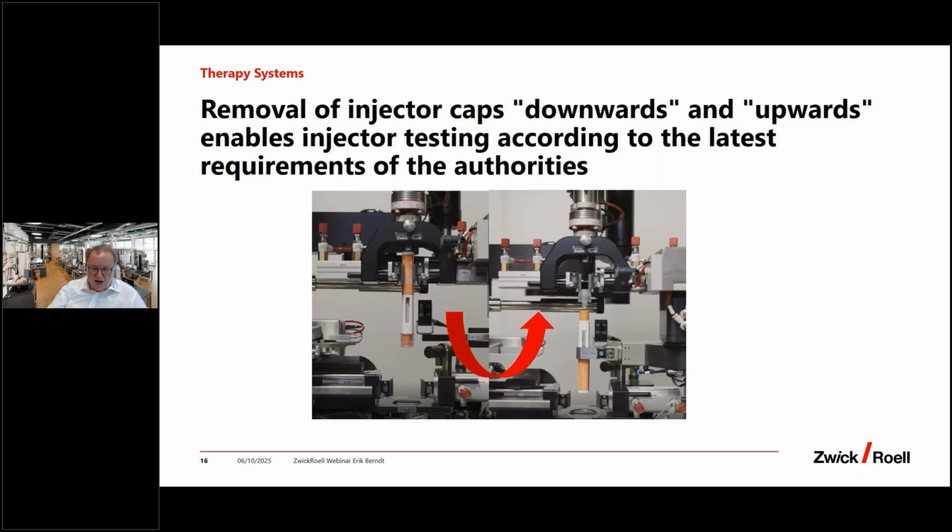It is now written that the patient has to remove the cap in the upright position, and this reduces the initial spilling. The topic is that the FDA came and said, okay, ISO 11608 tells you to follow the instructions for use, also for your test procedure. This was the reason we had to integrate the option to test with the needle in the upright position. I just told different device producers, and they told me that more low viscous drugs will be affected by this. We have some products, so this is quite an important option.